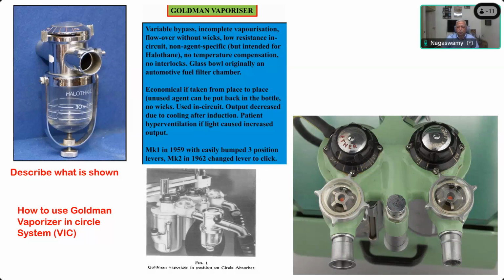And in the earlier picture, I asked you the question, what is the dial-like thing that is close to the oxygen flush? It was called the trilene lock in the older machines. So if you switch over to closed circuit from open circuit, the lever of the trilene vaporizer will not be operable. Okay, it will be stuck in off position. You cannot open the trilene vaporizer at all. So that was a safety feature incorporated very long back.